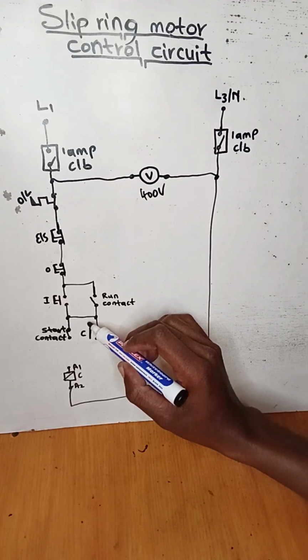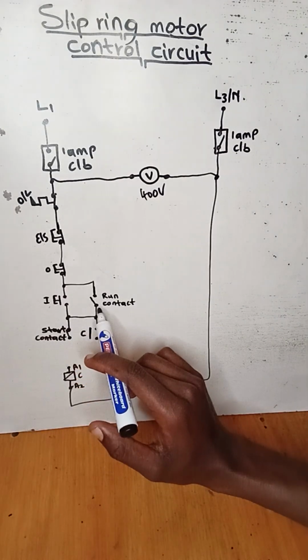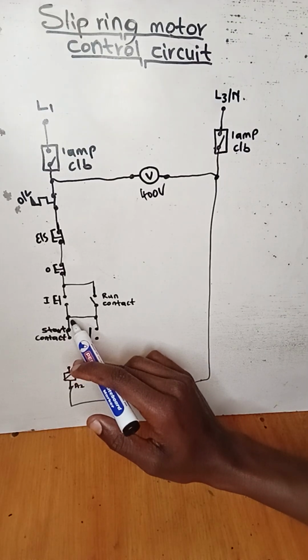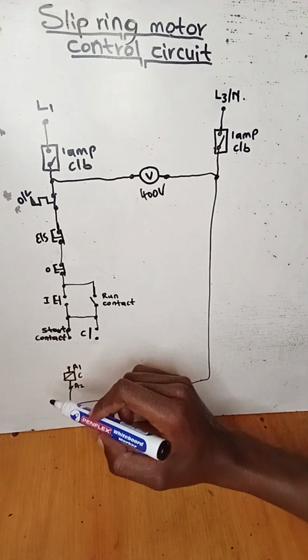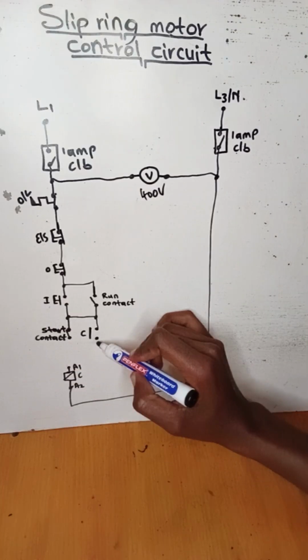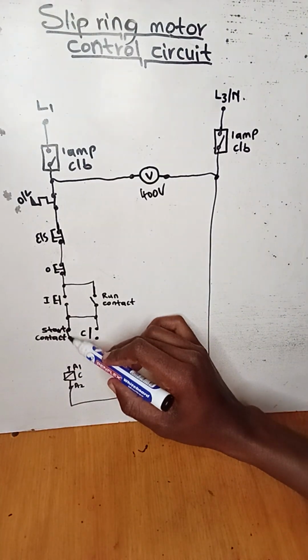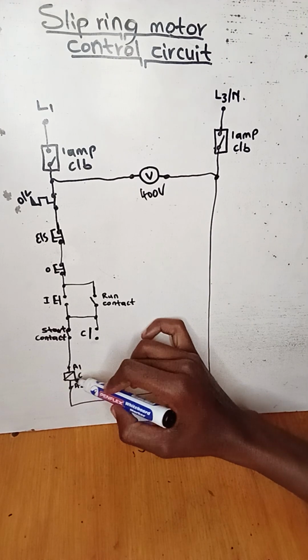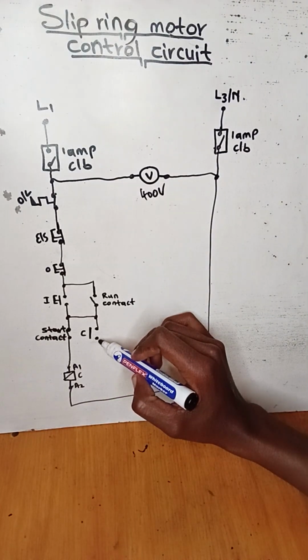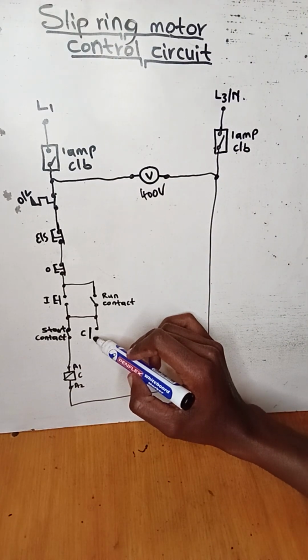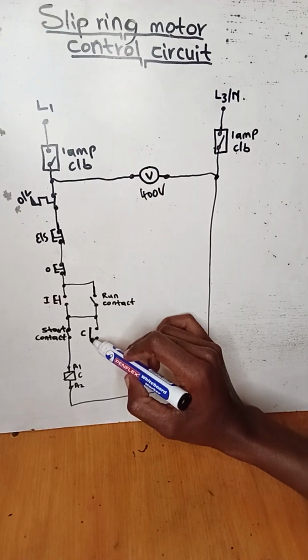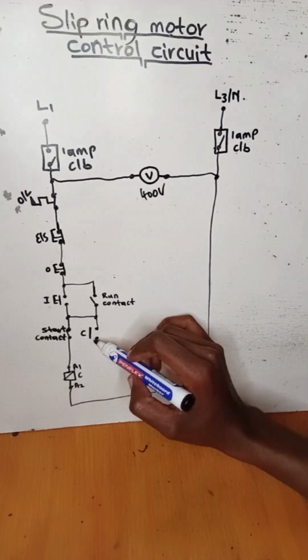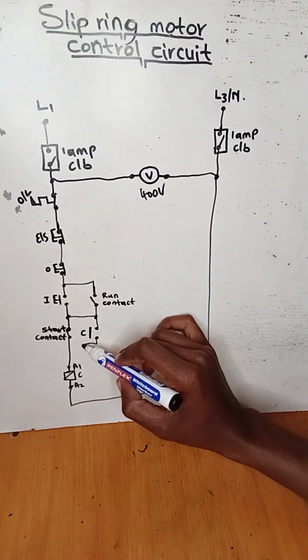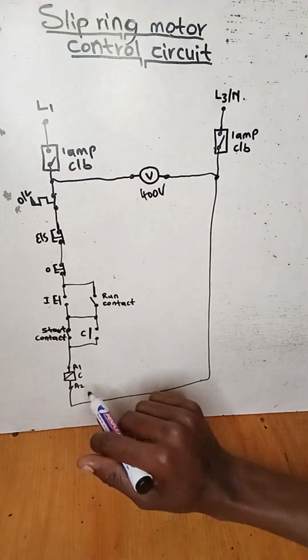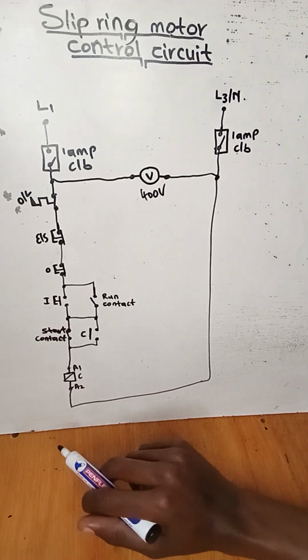The wire will be looped to the wire after the start button, right? And then after the normally closed contact of the start contact, it will be connected to A1 of the coil of the contactor, and then also the output of the normally open contact of the contactor, which is our retainer, will be looped all the way to A1 of the coil of the contactor, right?